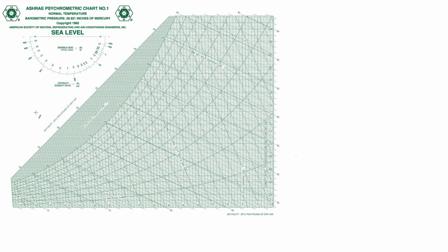So let's take a look at the psychrometric chart. Let's go through two different examples. The first example I want to look at is a case where we have only sensible cooling. So let's imagine it's a typical temperature in a room. Maybe it's 74 degrees and 50% humidity. And you're doing some cooling with a chilled water coil, but the chilled water temperature is warm enough that the cooling that's happening is only sensible. So maybe your chilled water temperature is pretty high, we'll say 60 degrees. Then your process line might look something like that, where this is state 1 and this is state 2.